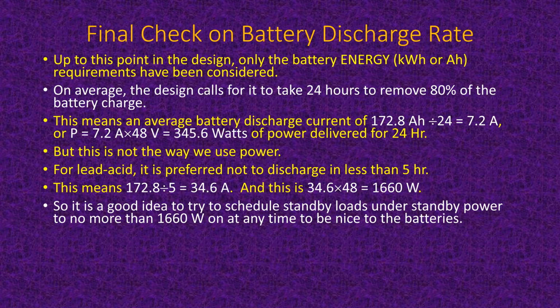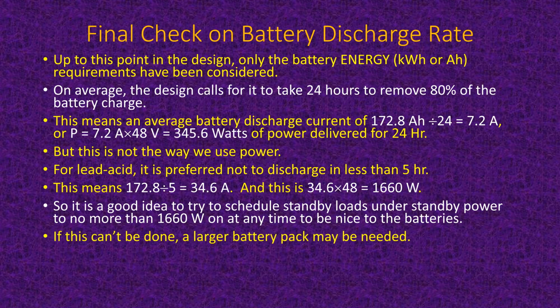Okay. So it's a good idea to try to schedule standby loads so that you don't use more than 1,660 watts at any one time. And if you do that, your batteries will be appreciative and they will give you more electricity than they might give you if you don't do that. So there's always a possibility of adding more batteries. And the more batteries you add, of course, the more kilowatt hours you can get, but also the more watts you can get. Because at that same discharge rate for twice the storage, you could go up to 3,320 watts instead of 1,660. All right, so that is an option.